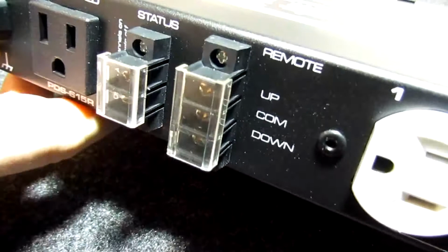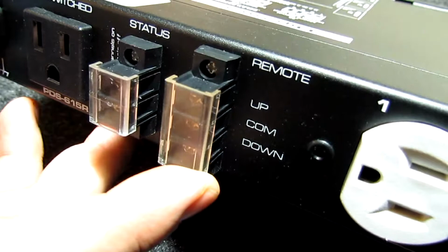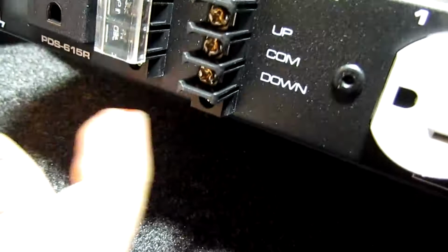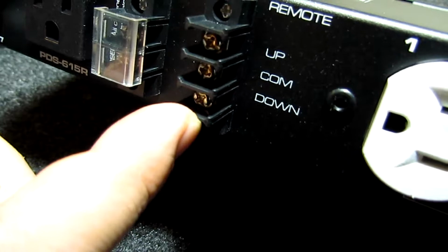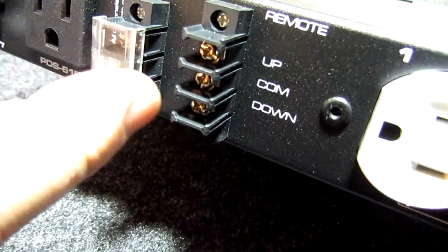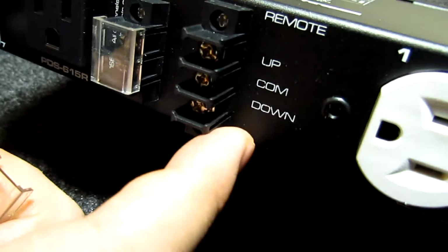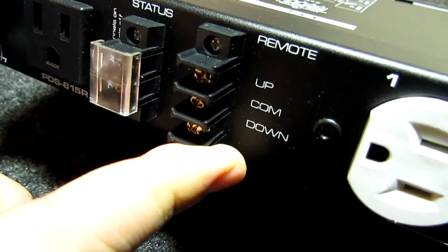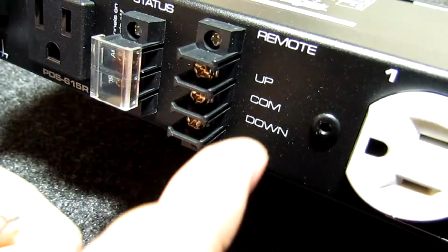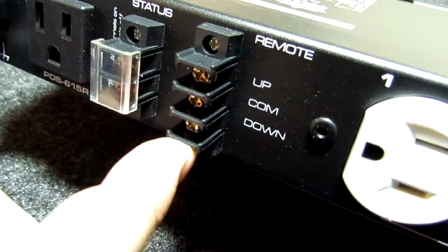This is what makes this thing unique, is that we've got this remote up down. So we can actually pop that piece of glass off. And what you've got here is just some screw terminals. And basically you can just take a 3 conductor cable, and if you wanted to wire 2 of these units together, this is how you do it. You would wire the remote up, comm, and down in parallel to a secondary unit. And up would be wired to the up of the second unit, comm to the comm of the second unit, and down to the down of the second unit. So you just want to wire it right in parallel there.